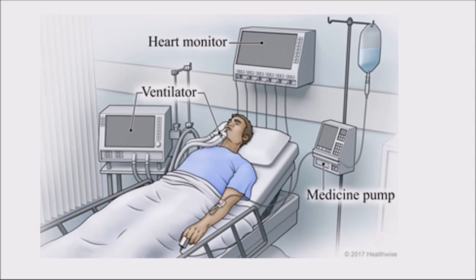Once we have this IV, it's attached to a pump, and our fluids in the hospital are pretty much always going through a pump now. In the operating room is about the only time we'll ever free flow fluids coming from an IV bag. And these IV bags should always be labeled, and they double check them, and they have a separate nurse come in and confirm that it's really the bag that they think it is. And we're very careful about that because that's one of the most common medical errors, these drugs, either the programming of the pump incorrectly or the wrong drug being hung.